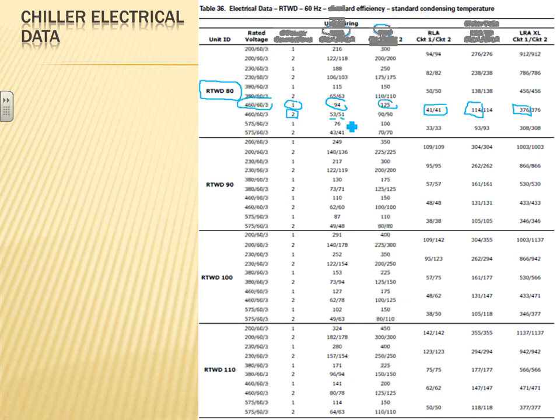So, smaller circuit breakers, smaller conductors, smaller conduits. I don't know, is there any other reason, any mechanical reason? Yeah. If you look at this one, a 125 amp circuit breaker might not coordinate with other things above it, since it's a bigger circuit breaker. If you cut them into two, it might do better coordination. It fits better in your panel. That's the only thing I can think of, because these are smaller loads. We can carry them, but it cuts the circuit breaker size inside your panel, as well as the overcurrent protection device. So if you have a short circuit, you can shut down part of the system. I don't know if it has to do with the operation of it too. Yeah, the multiple feeds.